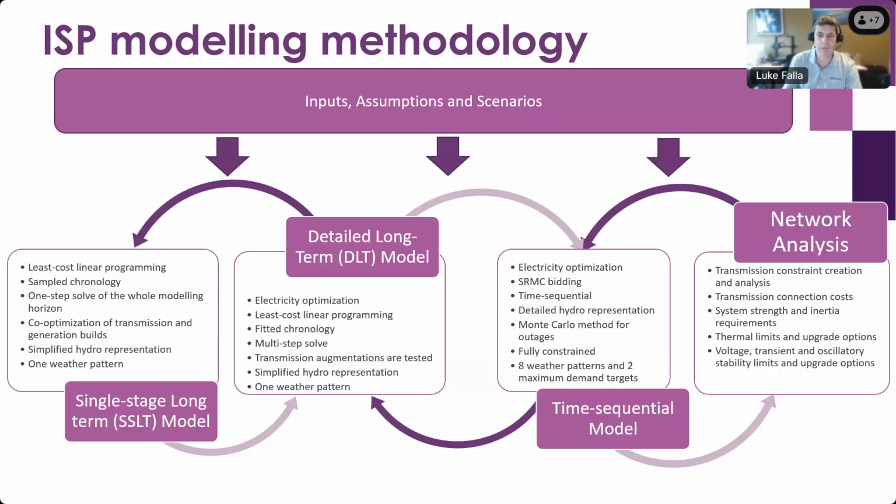So network analysis is not always just load flows. We sometimes will have limits such as what we call system strength. That's the need to meet fault current requirements for all the VRE and other issues like that. So we do look forward with that. There are some proxies used in fault circuit analysis or inertia studies as well, I think, things like that. So we try to have a whole representation of the system as a secure system that can be operated into the future.